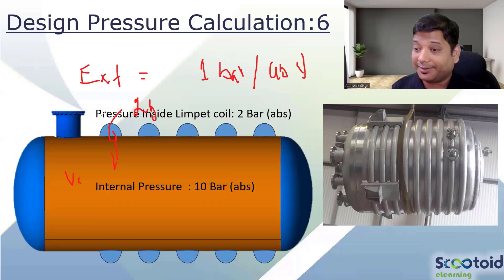If you have understood the external pressure calculation, length plays a very important role. See, this pressure in the coil, definitely it is acting as external, but it is acting at a very short length.